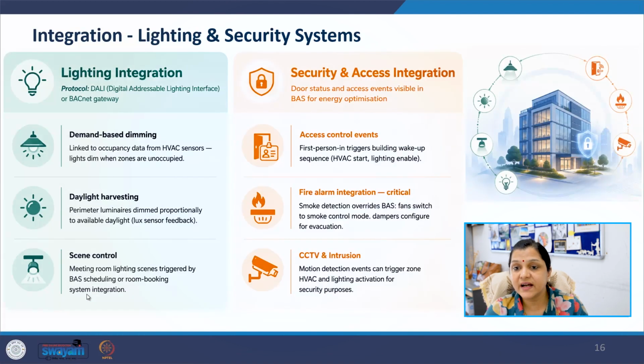Next is lighting and security integration. Modern BAS platforms also integrate lighting and security systems. Lighting systems may use DALI or BACnet gateways. Occupancy sensors can coordinate both HVAC and lighting operations. When a space becomes unoccupied, lights may dim automatically and HVAC operations may reduce.